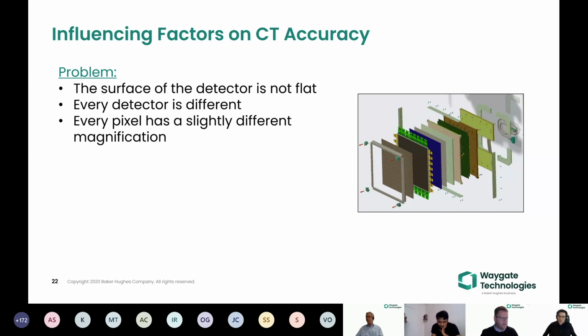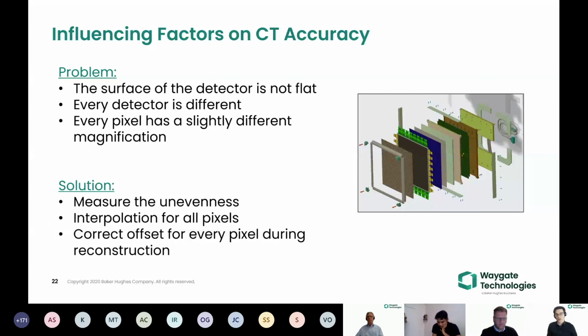Nothing in the world is perfect. And what does that mean? If we have a bent or slightly non-flat detector, each and every pixel has a different magnification, because one of the pixels might be in the corner, bent backwards, a little bit further away from our source than the one in the middle. So that gives us a different magnification for each and every pixel. That means a different voxel size for each and every pixel. We don't want that. So we came up with a sophisticated and now patented way of measuring this surface unevenness. And the thing always is, if we have measured it, if we know it, we can correct it and compensate for it. So for each and every pixel, we know exactly how big the offset is, and then we can correct it, and then everything is virtually flat.